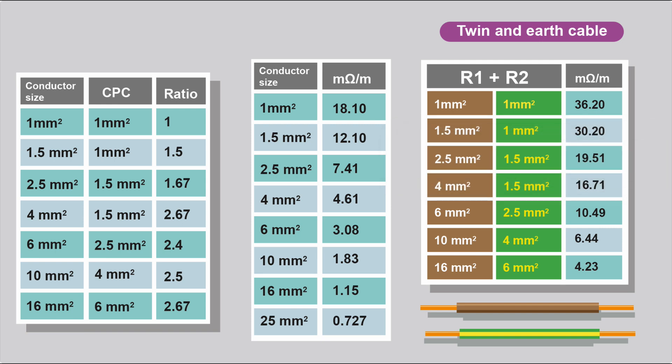And all I've done, as you see here, the 2.5 and the 1.5, they added the two columns together. So to save doing two calculations and then adding the results together, you can just combine the 2.5 and the 1.5, you'll get a milliohms per metre value of 19.51. And this is the value that you'll use when you're working out the length. We'll do an example.